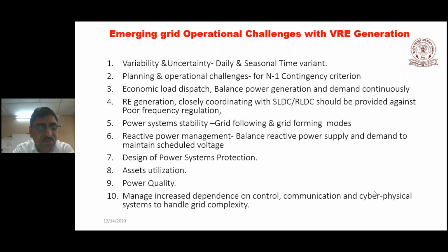So the protection relay gets confused trying to identify whether it's really a fault or just normal operation due to variation in wind speed. Briefly, the protection we have today is quite reliable, but only as long as we have a synchronous machine at the source. If we replace it with PV-based or wind-based systems, the reliability will not be what we expect, so we have to look for alternate protection-based systems.